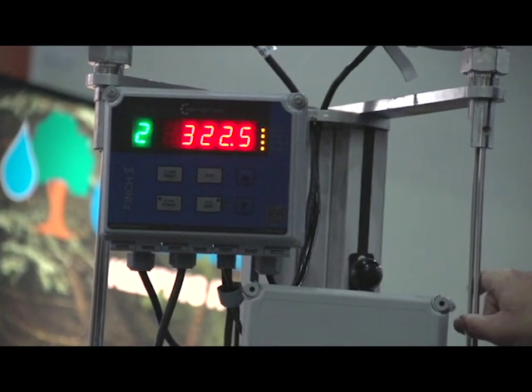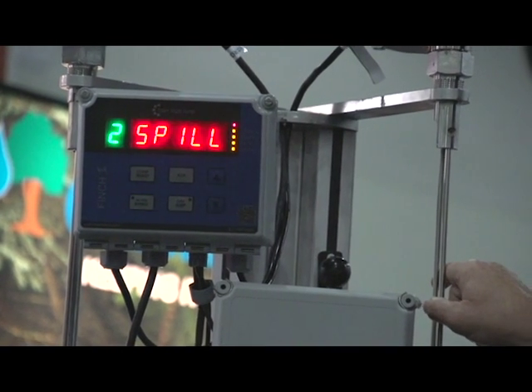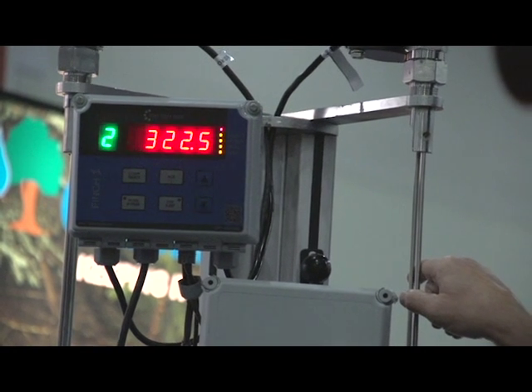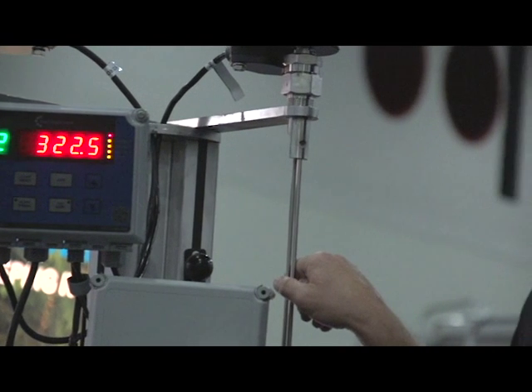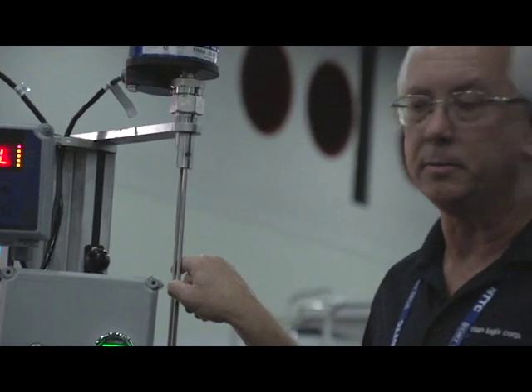If he hits the spill level, it's a totally fail-safe system and he cannot reset that. Once he hits that, the only way to get it out of spill is to offload oil. There is virtually no way to have an overfill in the Titan Logic system.